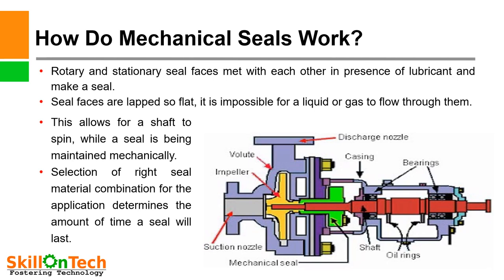How do mechanical seals work? A picture of a pump is given in the slide. Rotary and stationary seal faces mate with each other in the presence of a lubricant and make a seal. A lubricant may be a process fluid or an auxiliary sealant. Seal faces are lapped so flat within three light bands that it is impossible for a liquid or gas to flow through them. This allows the shaft to spin while a seal is being maintained mechanically. In a pump, the shaft is in a rotating condition, and the rotary unit of the mechanical seal also rotates along with the shaft, while the stationary seal ring is fixed in the casing.